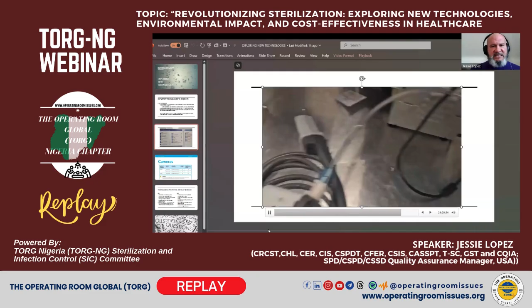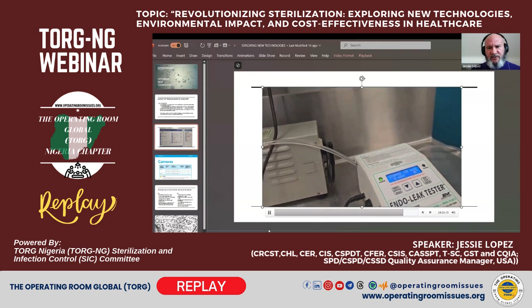30 seconds later, you don't see any bubbles emerging out of the water. So this device has been cleaned properly and the integrity is safe. So we can go ahead and go to the next step of the process here. We're going to turn off our leak tester here, make sure it drops down to 0. We're going to disconnect it from the device. And then the next step.